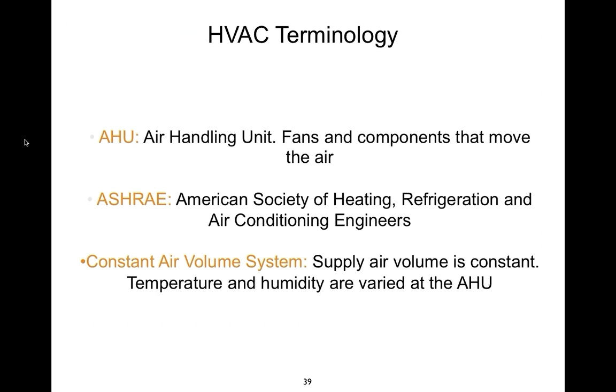Here are some coils, a typical cooling coil with a condensate pan. It's got a little trap in it to keep sewer gases from backing up and getting pulled in. Remember, the coils may be under negative pressure, so that condensate pan is under negative pressure too, which means the pipe coming off it is under negative pressure. If you connect it to a sewage line, it's going to suck sewer gases out of the line and back up into the unit. So there's usually a little water trap before it goes to a drain.